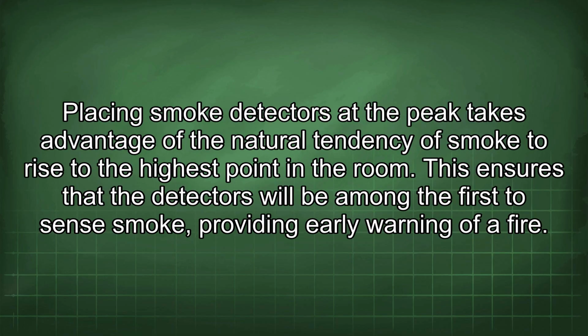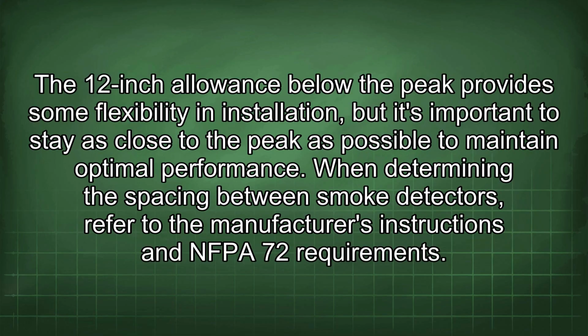Placing smoke detectors at the peak takes advantage of the natural tendency of smoke to rise to the highest point in the room. This ensures that the detectors will be among the first to sense smoke, providing early warning of a fire. The 12-inch allowance below the peak provides some flexibility in installation, but it's important to stay as close to the peak as possible to maintain optimal performance.